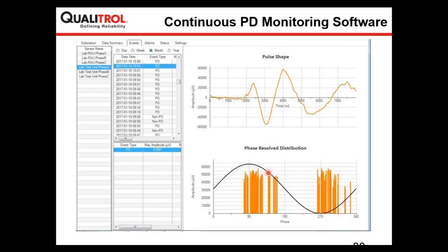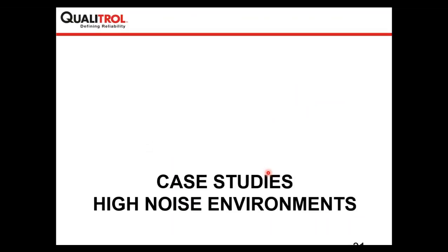If you want to have a detailed webinar, we can also do that. Whenever you have experience with online partial discharge measurement, or if you read the literature, the biggest challenge for performing online partial discharge measurement is the external noise or the system noise which is present inside the system.